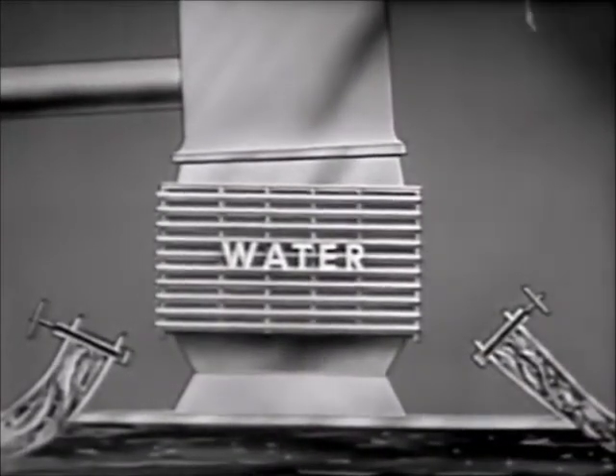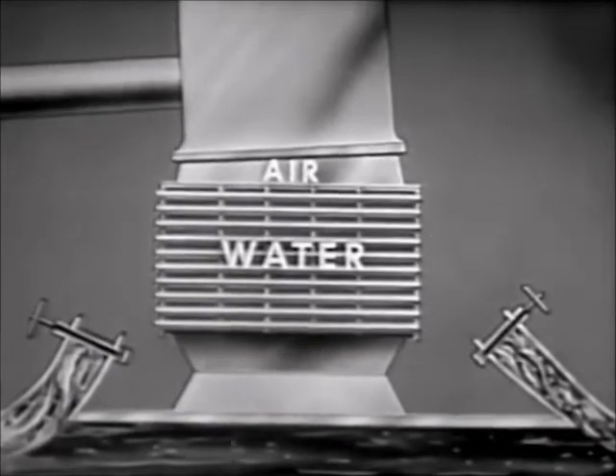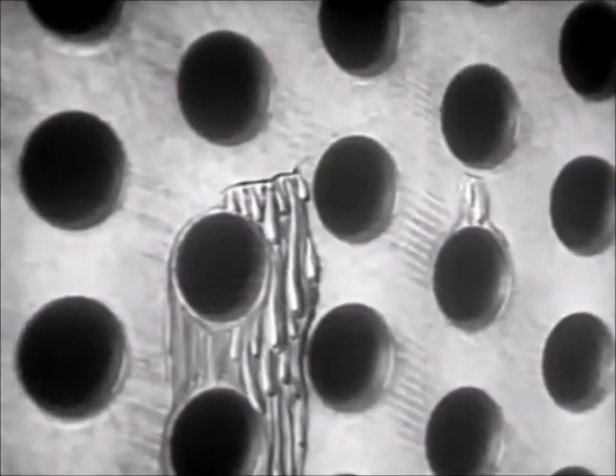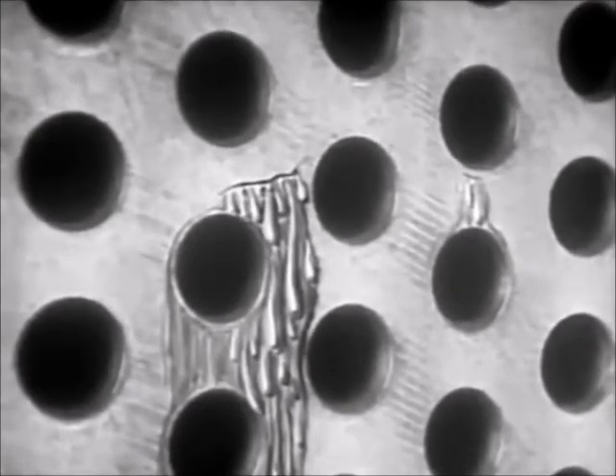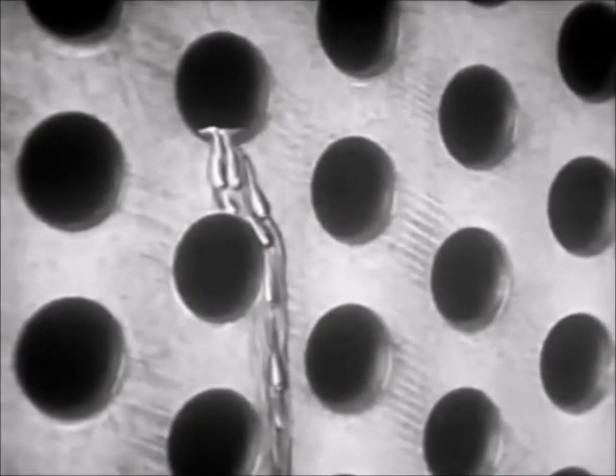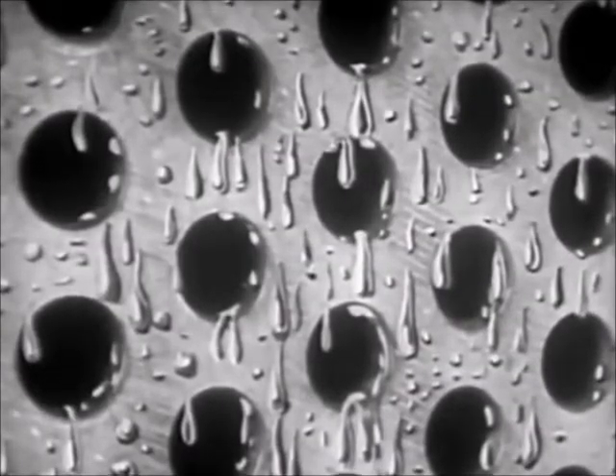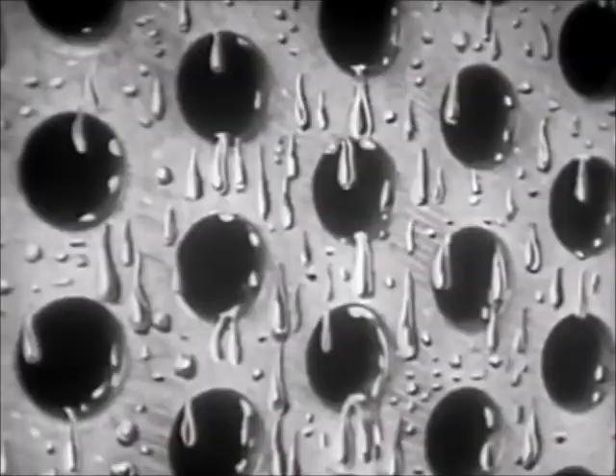In another method, the water pressure method, fill the steam side with water to cover the tubes, and then introduce compressed air to force the water out through any leaks. Water coming through the tube sheet area can be traced directly to a leak, and water dripping from a tube indicates a leak somewhere in that tube. If any condensation forms, blow it dry using an air hose.